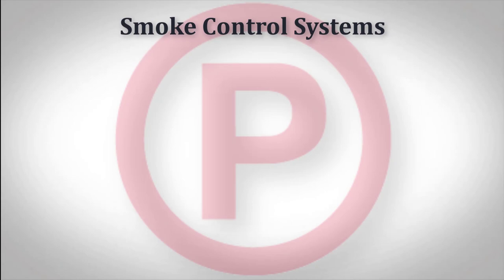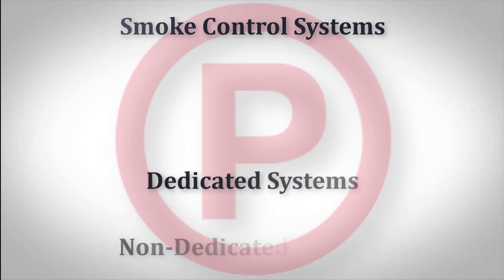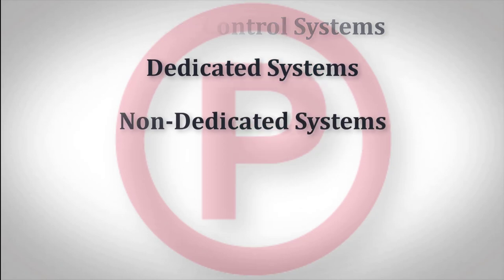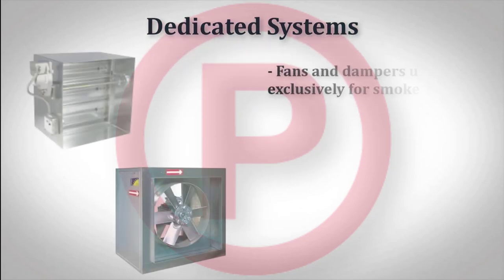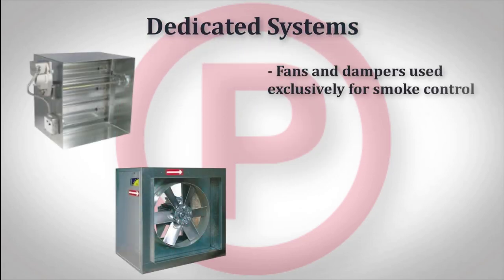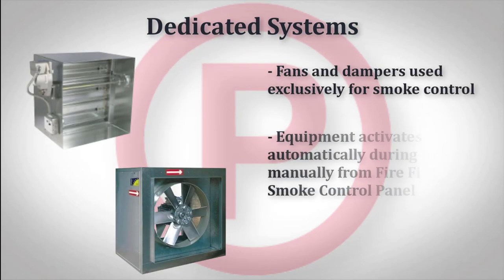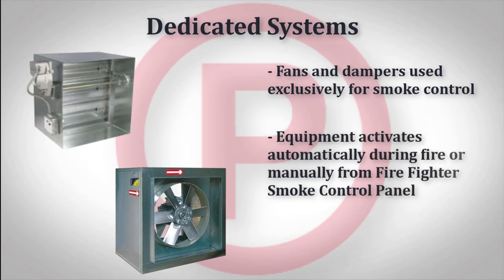Smoke control systems can be configured in two different ways: dedicated or non-dedicated. Dedicated systems are used exclusively for smoke control. Fans and dampers activate automatically, but only when there is a fire or when manually activated by the firefighter's smoke control station.